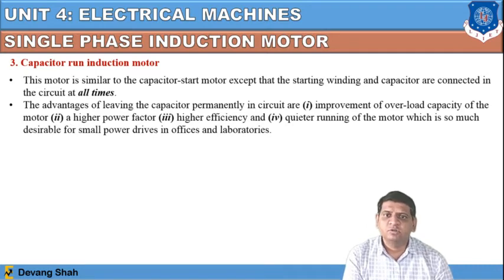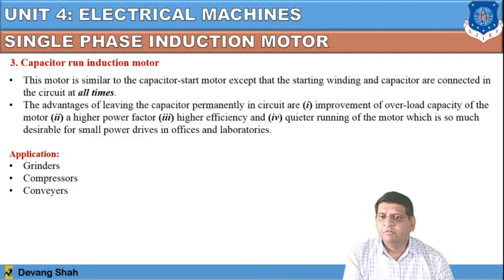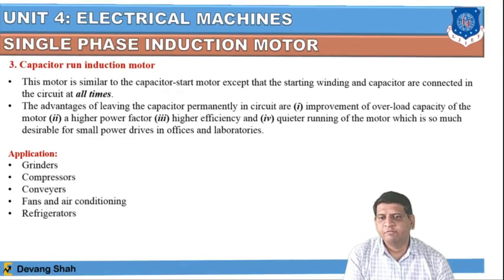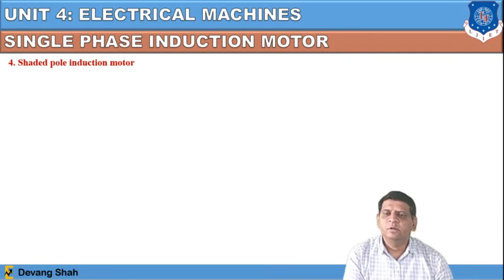There are certain advantages of leaving the capacitor permanently in the circuit, like improvement of overload capacity of the motor, higher power factor, higher efficiency, and quieter, smooth running of the motor, which is very desirable for small power drives in offices and laboratories. Overall, applications of this single phase induction motor include grinders, compressors, conveyors, fans, air conditioning and refrigerators, all of which can use the capacitor start, capacitor run type of induction motor.